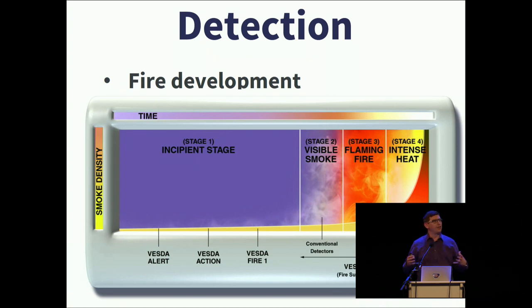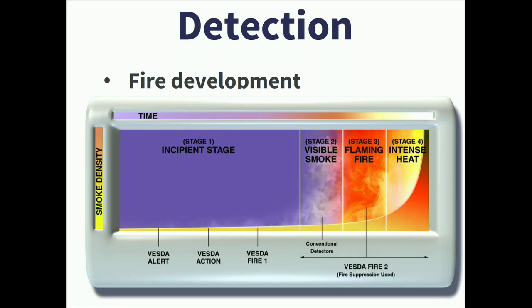And if you look at fire development, there are distinct stages in that fire development. And importantly, with the VESDA system, at the incipient stage of a fire, there are small particles being given off. And this is before it's started to generate heat or lots of black smoke or the such. And a VESDA system will create what is generally called a VESDA alert or a VESDA pre-alarm, saying something's going on with the air quality. Chances are we're detecting the very early stages of combustion.